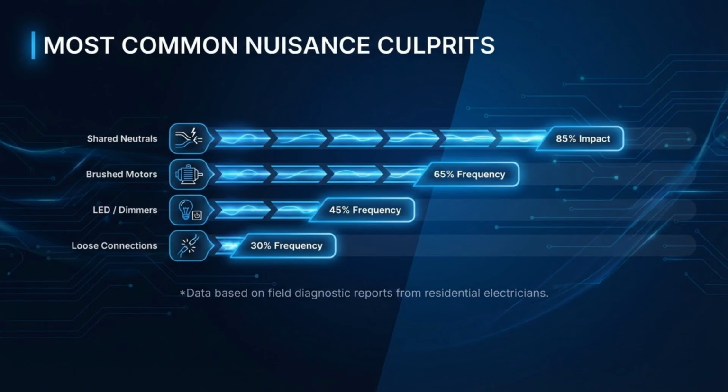Based on field diagnostic reports, shared neutrals are the most impactful nuisance culprit. Brushed motors are a common trigger, followed by LED/dimmers and loose connections.